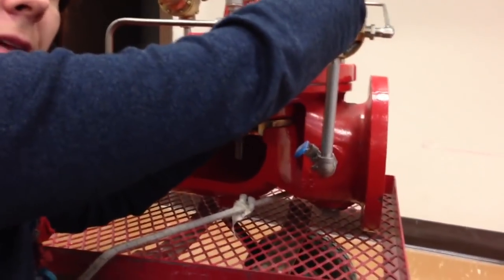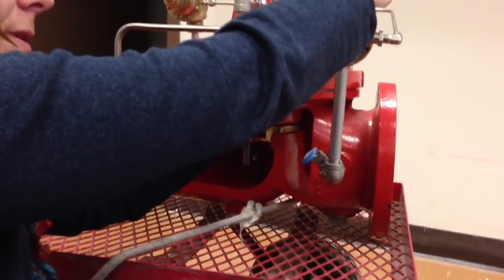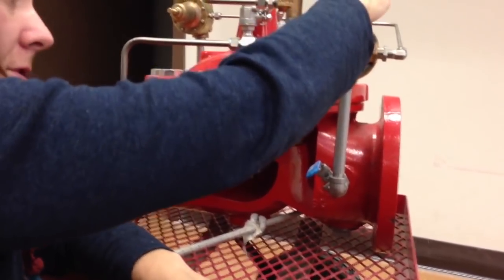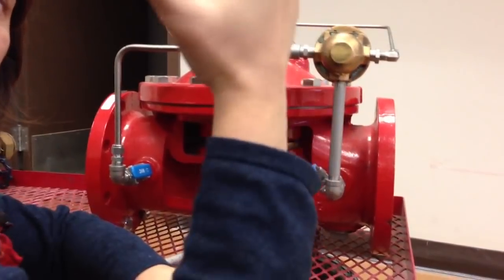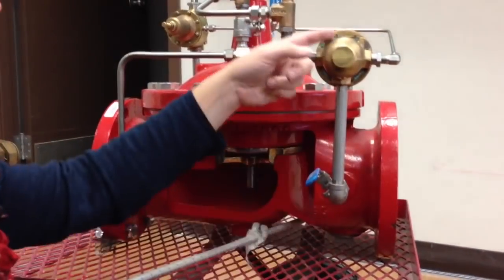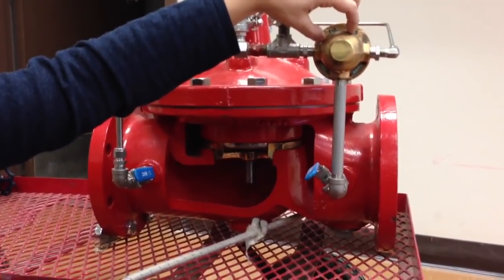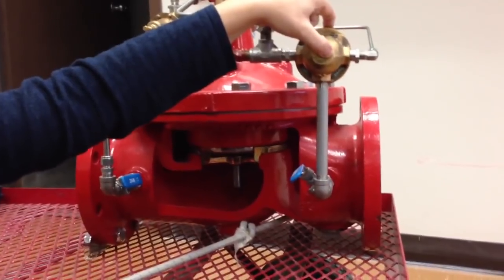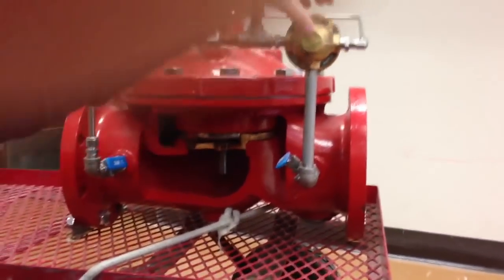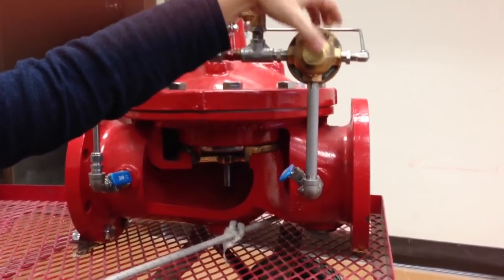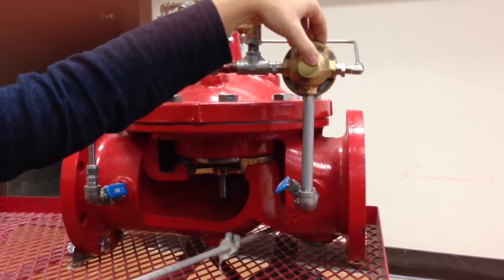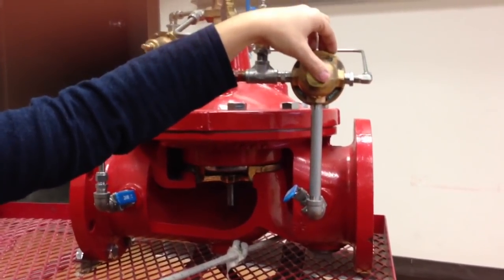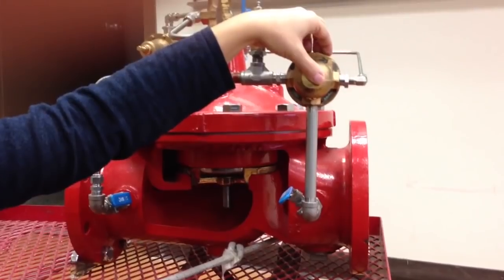top of the bonnet, in the valve chamber on the top. So when that happens, the only force that's acting on this is the stem, the spring force, which is going to force the stem in this direction, which will then move the saddle assembly away from the seat, opening this valve. So this valve is going to fail open. So when we talk about a pressure reducing valve like this, this is a reverse seated, normally open valve. Right, because it fails open.